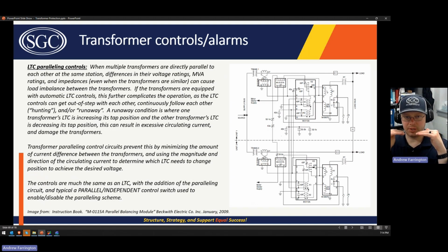So the paralleling controls make it so that only one LTC operates at one time, and it determines which one should operate based on the circulating current that's flowing between the transformers. If one transformer taps up, there's going to be a current imbalance between those two transformers, because one is going to have a different turns ratio than the other. So there's going to be slightly more current in this transformer versus this one based on that tap position, and some of that current circulates around in the transformers. What you don't want is those two taps to get too far away, because then you can cause excessive heating in your transformers, and that would be bad. So those are the two reasons you want those LTC positions to operate as a unit.